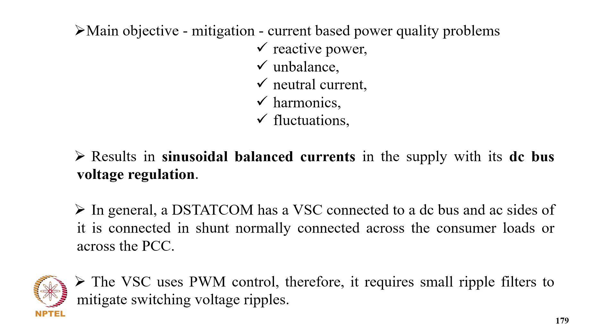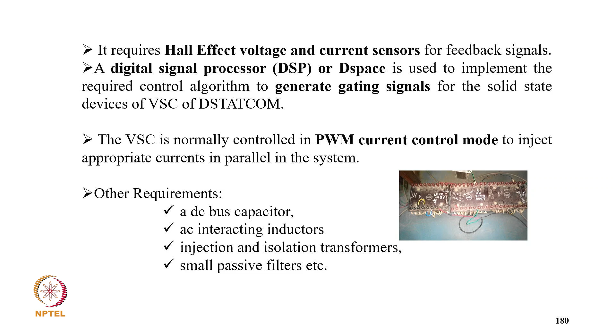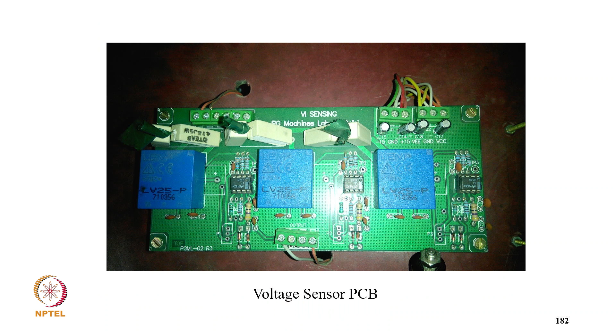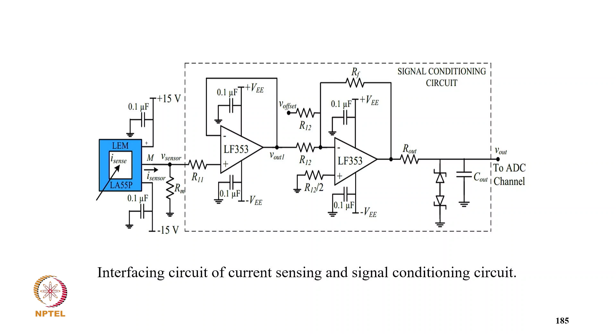It also requires Hall effect voltage and current sensors for feedback signals. A digital signal processor like a dSPACE is used to implement the required control algorithm to generate the gating signals for the solid state devices of the voltage source converter of the D-STATCOM. The voltage source converter is normally controlled in PWM current control mode to inject the appropriate current in parallel in the system. Another requirement is a DC bus capacitor, an AC inductor, an injection or isolation transformer, and a small passive filter. These are typically the hardware prototype, and this is the voltage sensor PCB, with the remaining sensing and conditioning circuit so that you can connect to the ADC. Then you have a current sensor hardware PCB, and this is the interfacing of the current sensor. You can clearly see how the current sensor works properly.